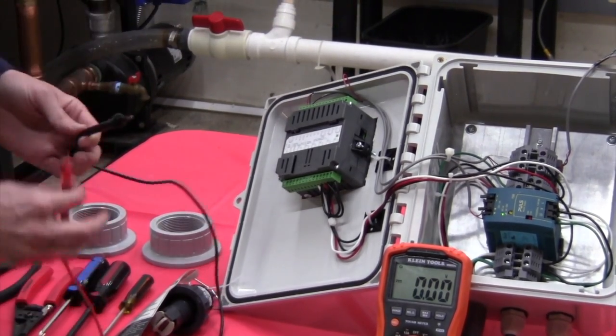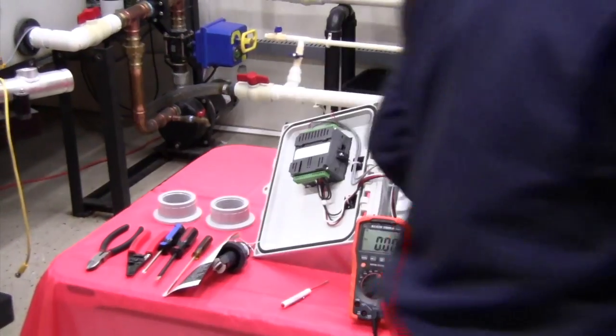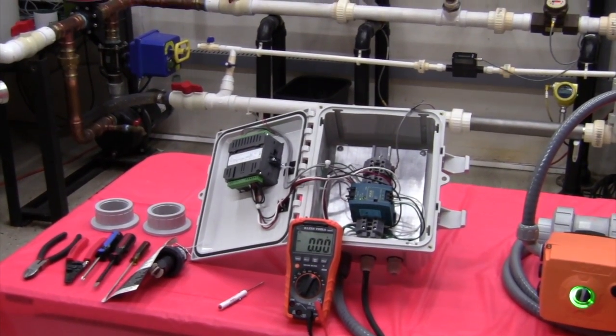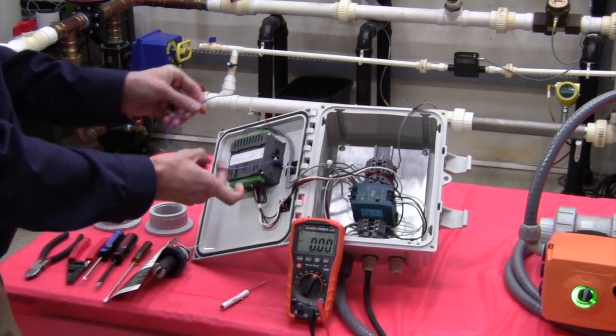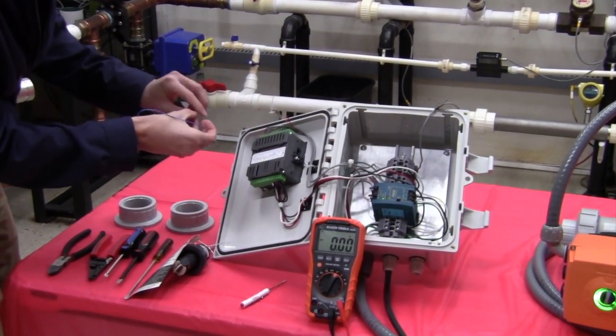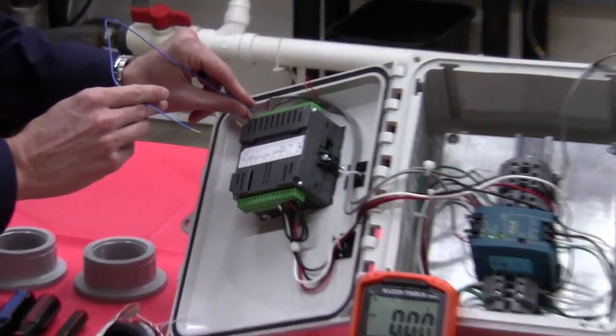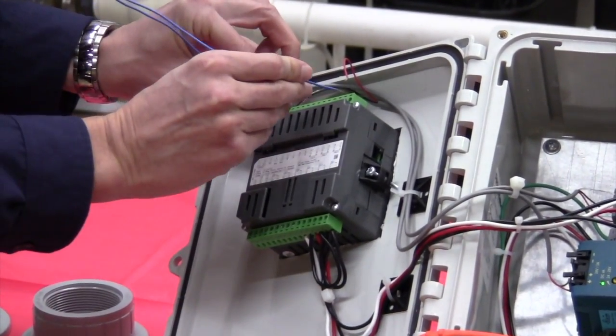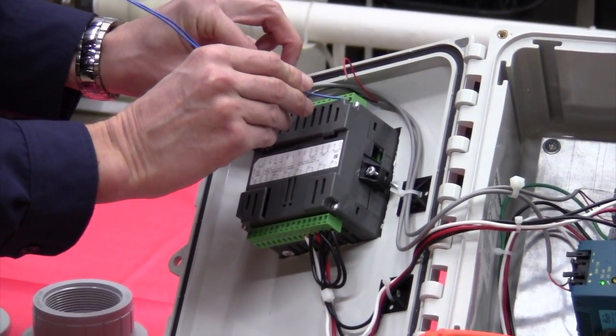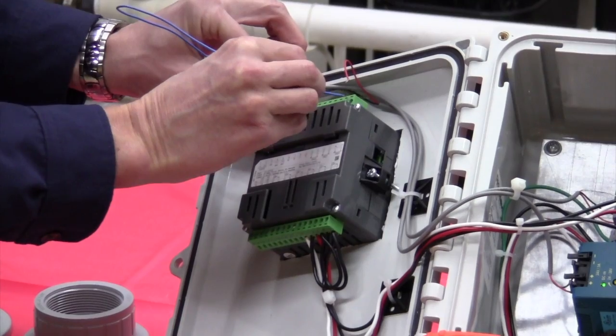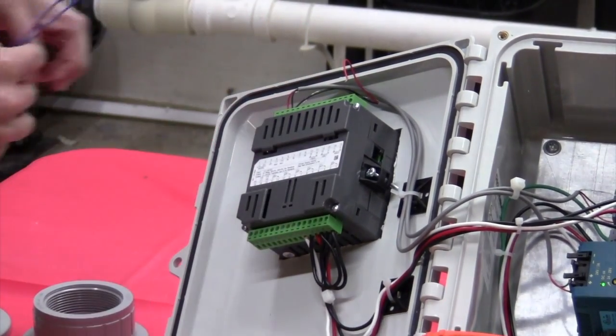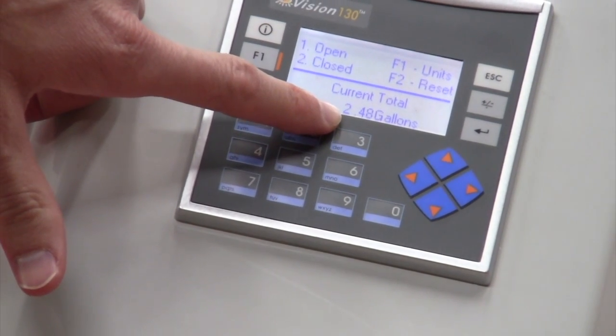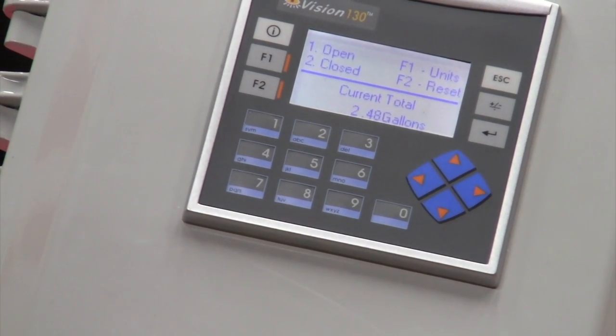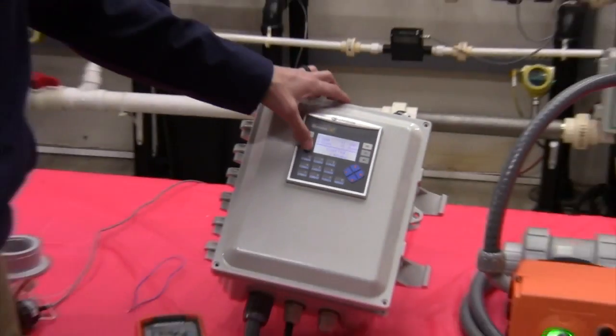The last thing that you can do for troubleshooting is take either a paper clip, or in this case, I have a jumper wire. If I take one end of my jumper wire, put it on terminal 2, and tap the other end on terminal 15, that is the same thing as creating pulses. I'm simulating pulses by doing this. If I then look at my display, you can see that I've totalized. I'm up to 2.5 gallons. So again, that's testing the inputs on the display. Everything is functioning properly, just as we would expect.